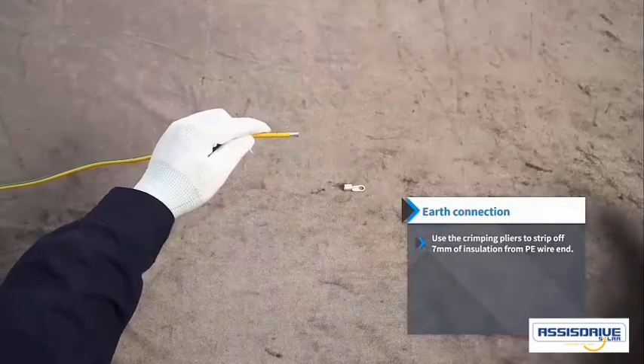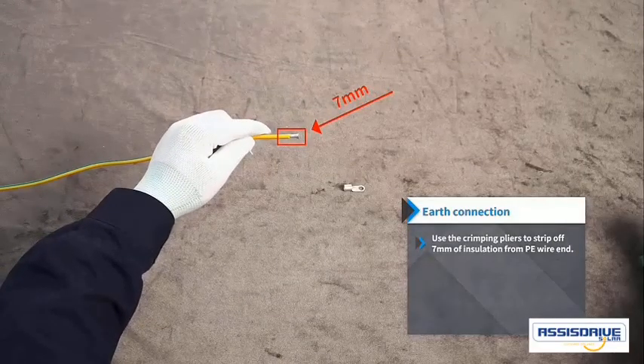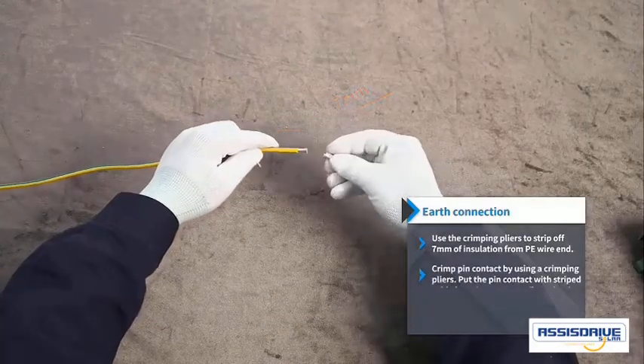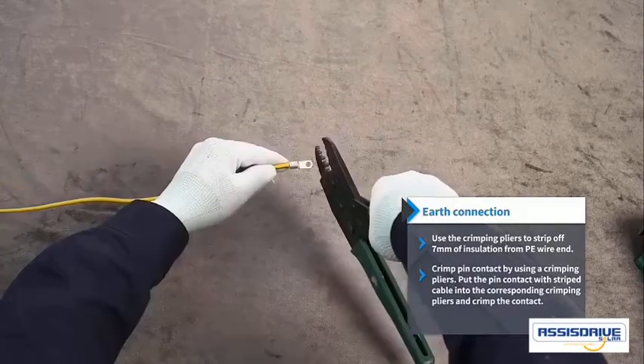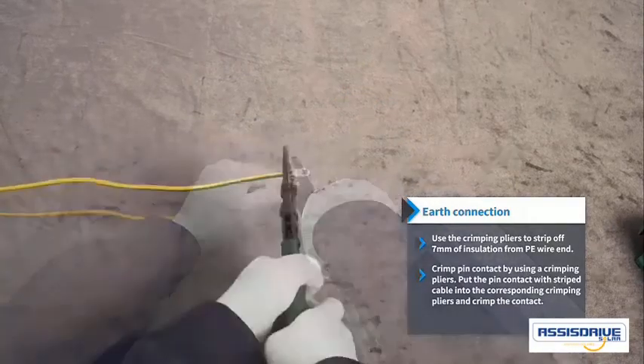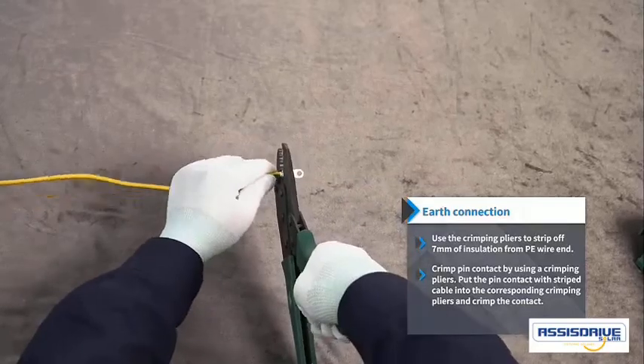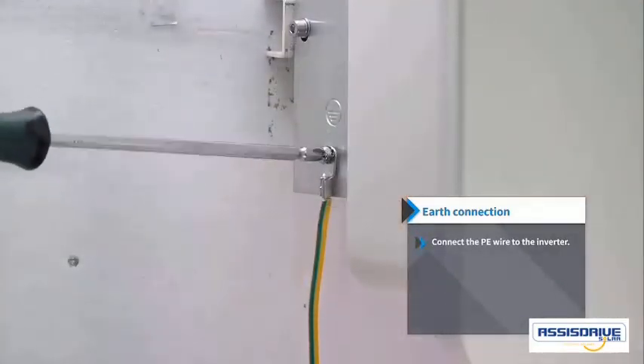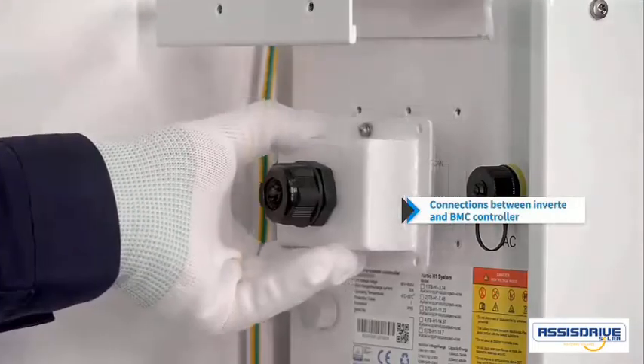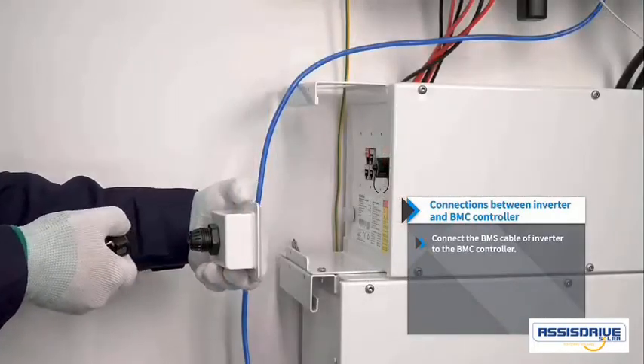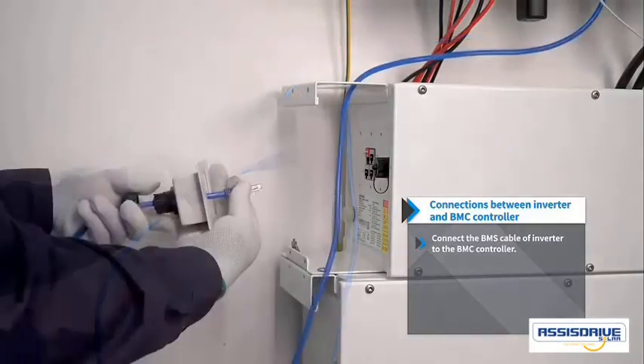Earth connection. Use the crimping pliers to strip off 7 mm of insulation from PE wire end. Crimp pin contact by using crimping pliers. Put the pin contact with stripped cable into the corresponding crimping pliers and crimp the contact. Connect the PE wire to the inverter. Connections between inverter and BMC controller. Connect the BMS cable of inverter to the BMC controller.